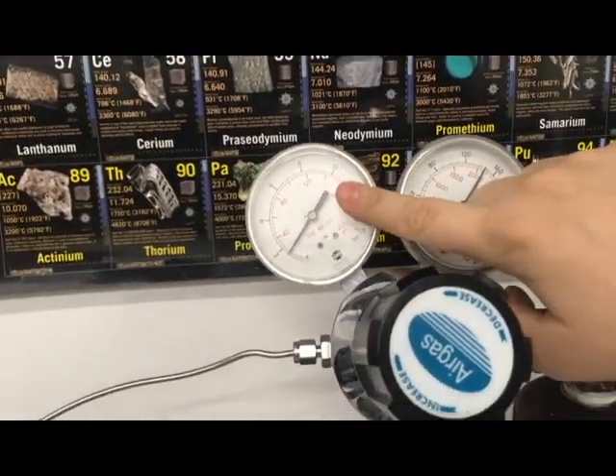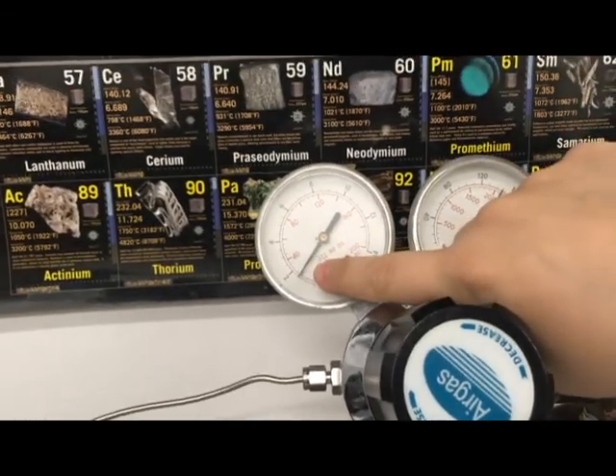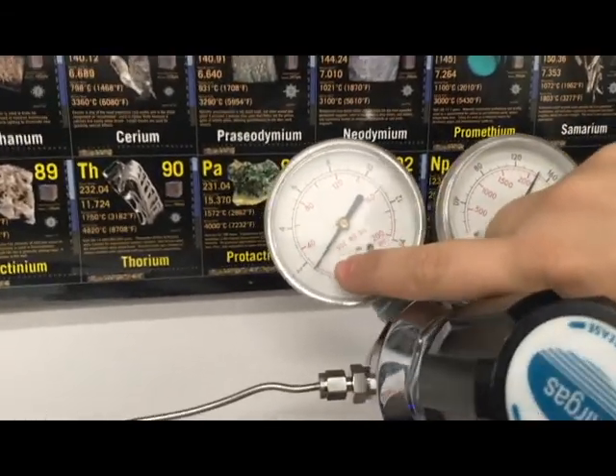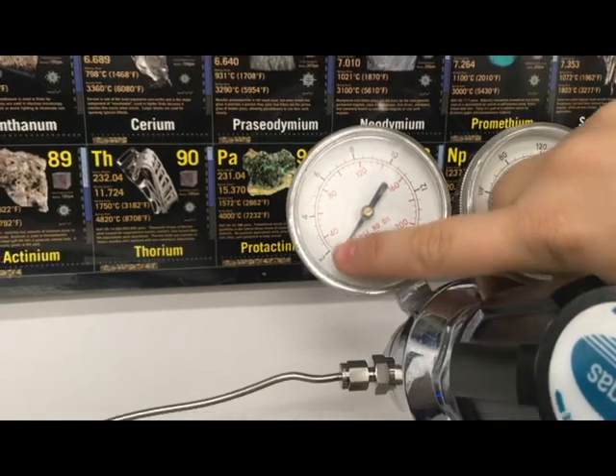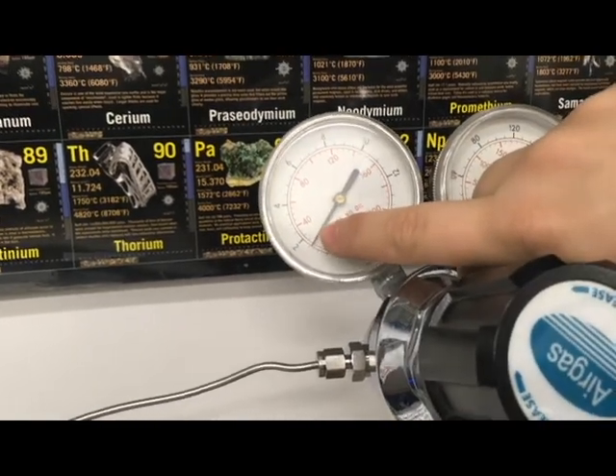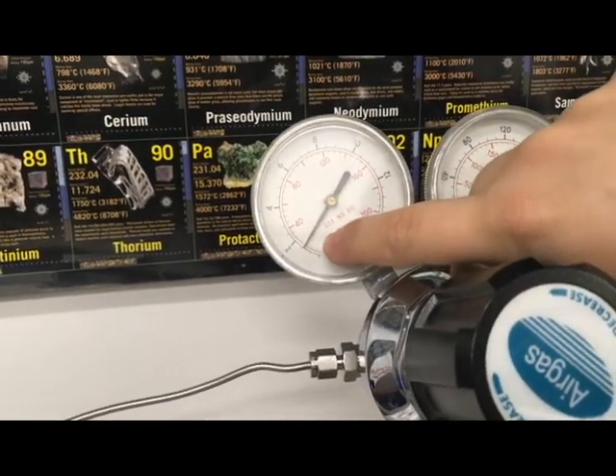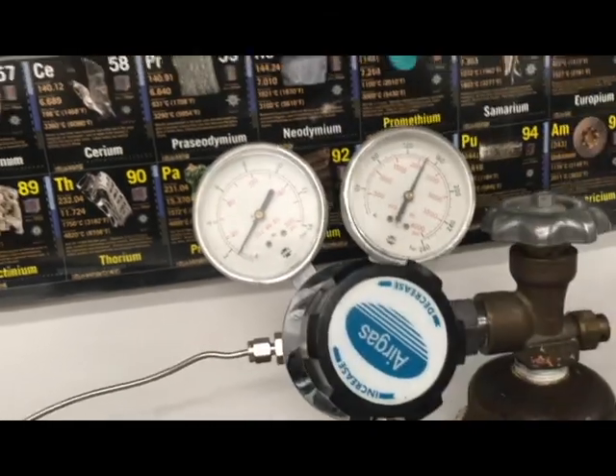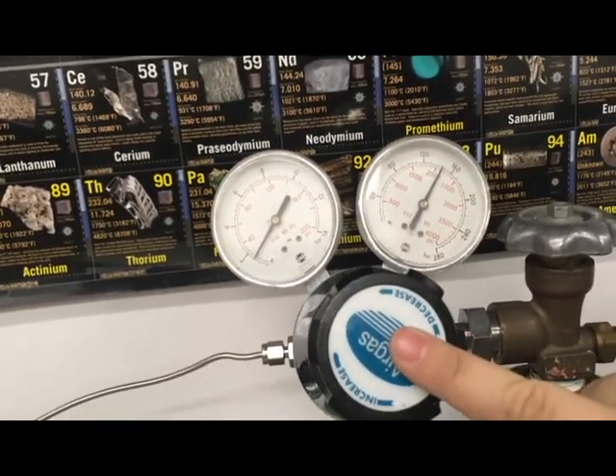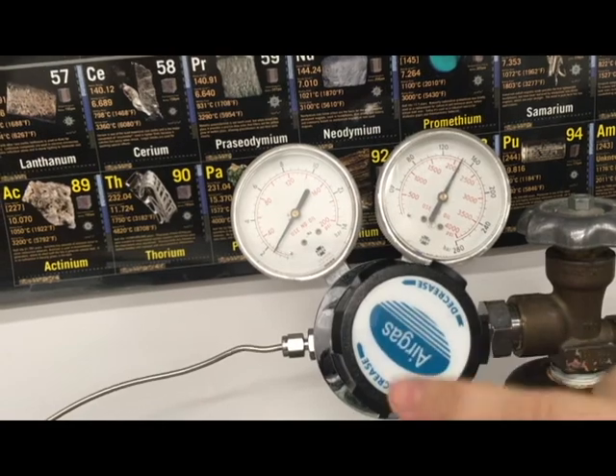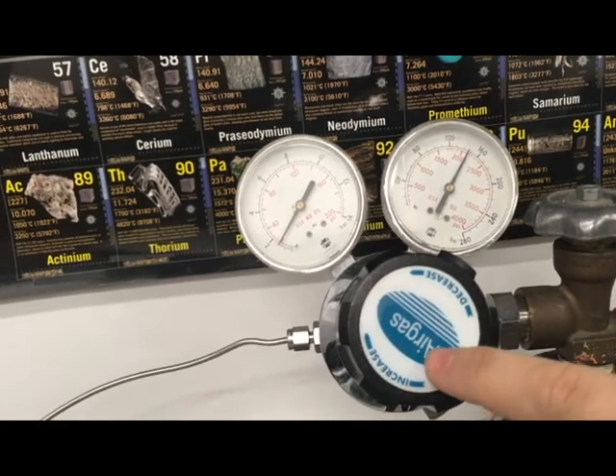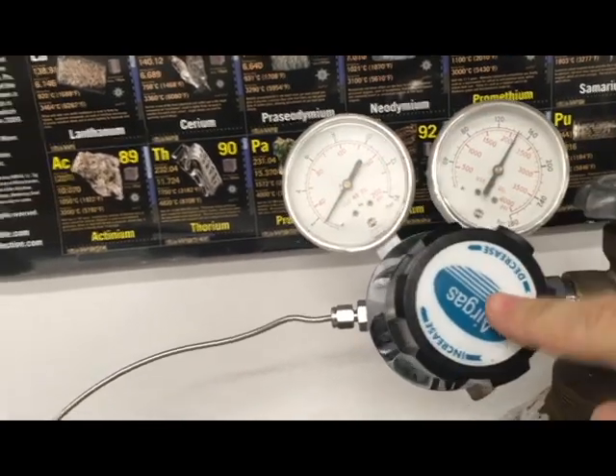This right here is the output pressure. The maximum that we'll see on the Ultrapyc is 20 psi, which is where it's set right now in those red numbers. It will be set anywhere between 20 and lower down to about 2 psi. You can change that by adjusting this knob right here. You can see arrows to decrease or increase the pressure coming out of our regulator here into the Ultrapyc.